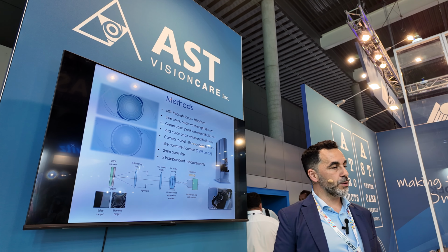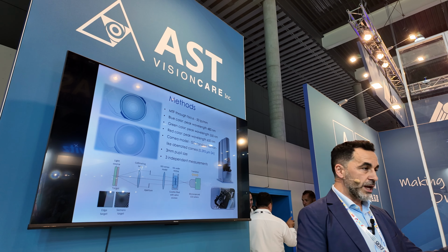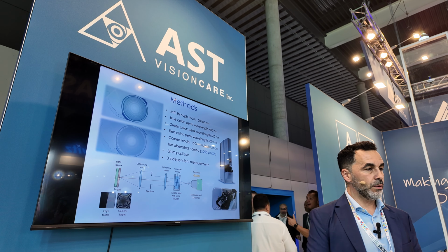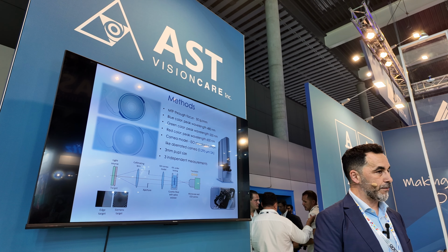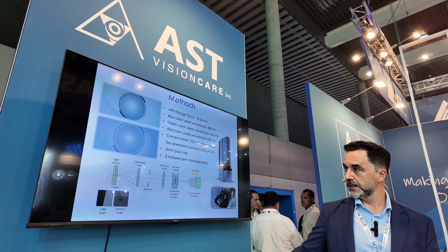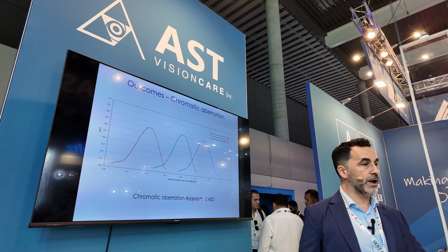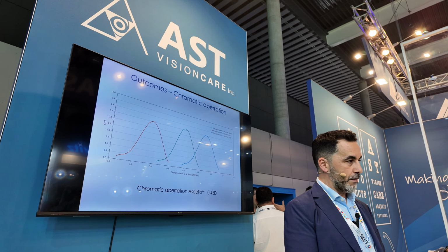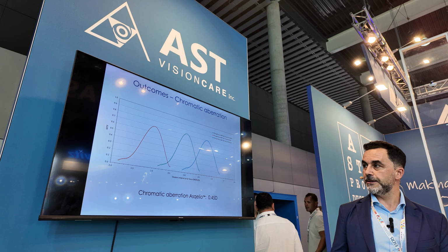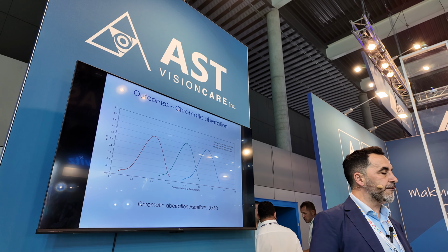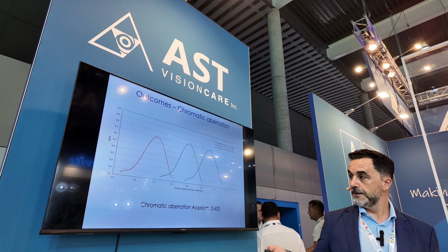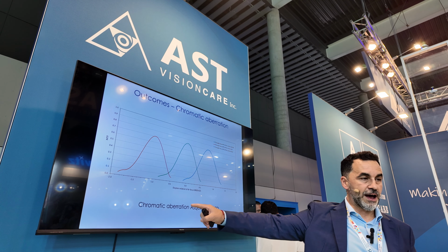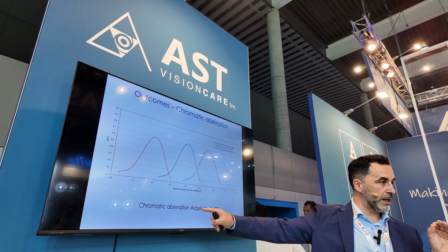And we did three repeated measures for each of the lenses, well centered, and I'll show you the results for the three lenses. For that we used the PMTF, which is a very widely used optical bench device for measuring performance of IOLs. So this was what we obtained for the monofocal IOLs. This is a through focus MTF for 50 line pairs per millimeter.